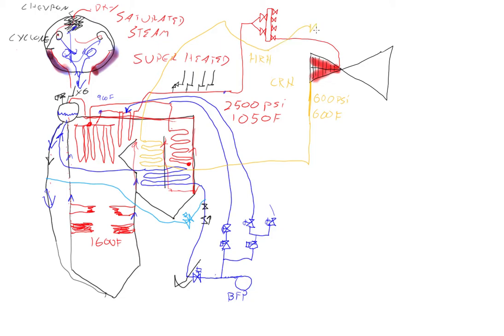Then we go through the intercept valves which are similar to the main steam stop valves, they're spring to shut, hydraulic open. Now we are at say 590 psi because whenever you travel down a tube you lose pressure from resistance, but we are at 1,050 Fahrenheit again.